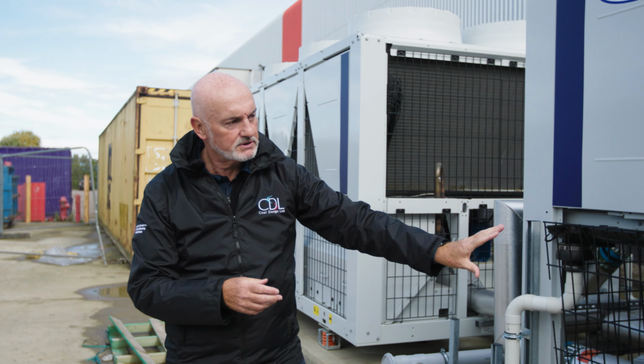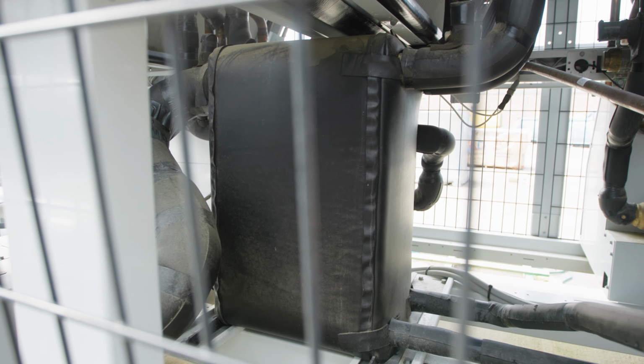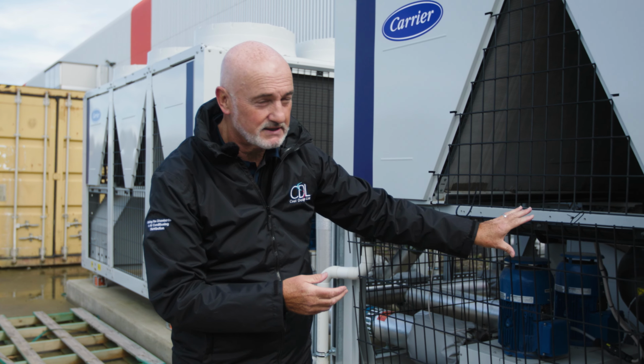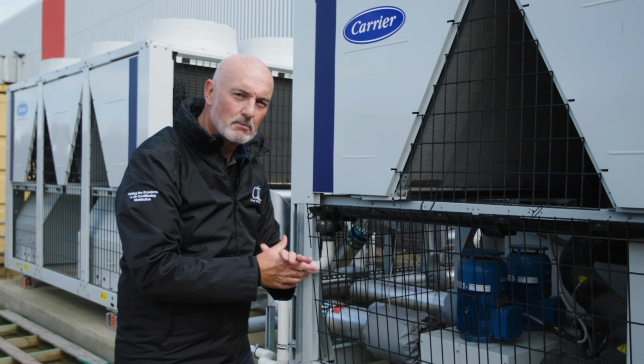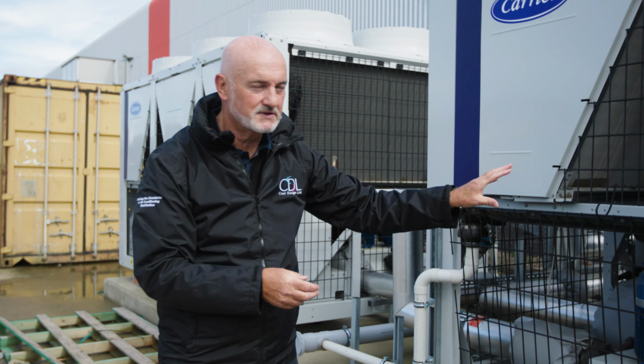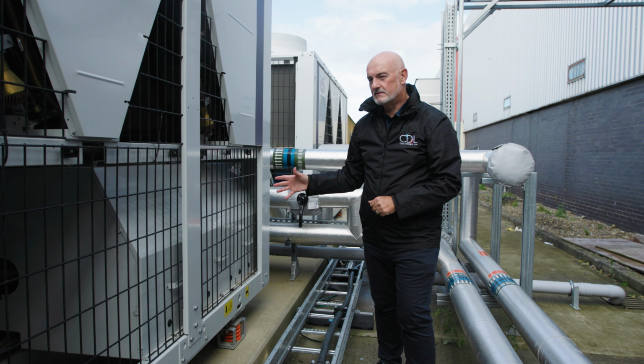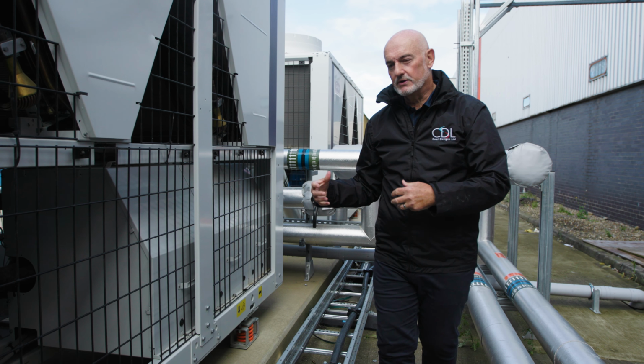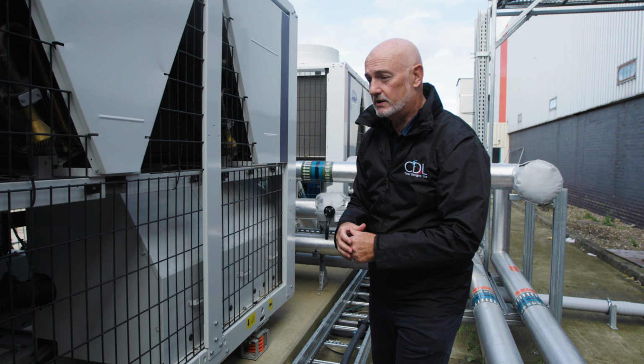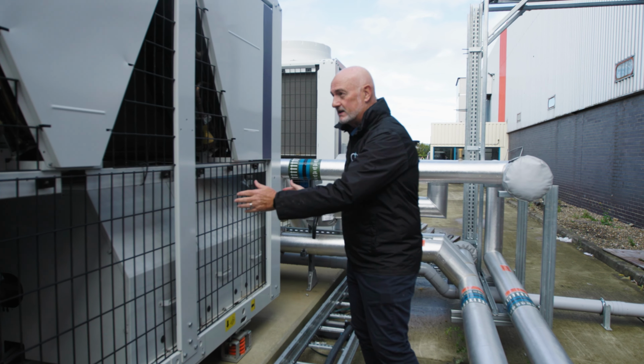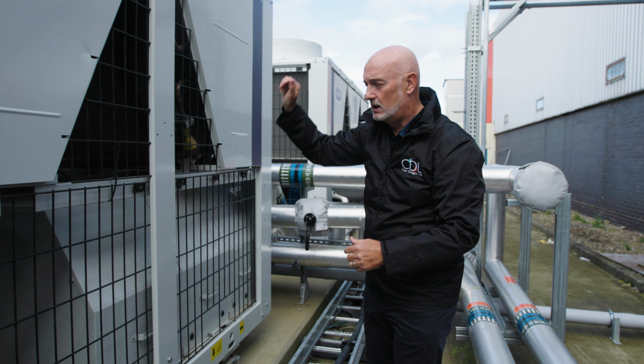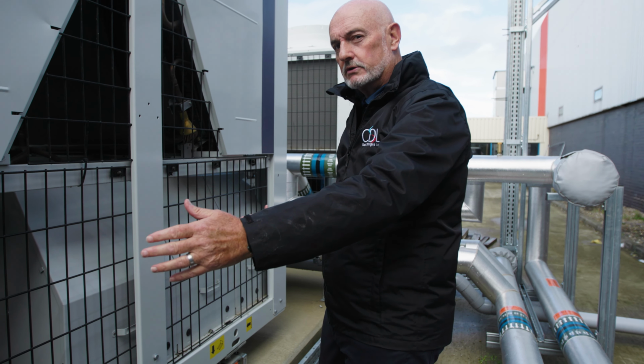And there's a little black box in the center there, which does the heating. And that is the same as the S-shaped thing at the back of your fridge at home. It gives heat out. This air source heat pump's main energy draw, the COP, the efficiency of the machine and everything, is basically the compressors and the fans. The fans are quite small. The compressors are the main electrical draw.